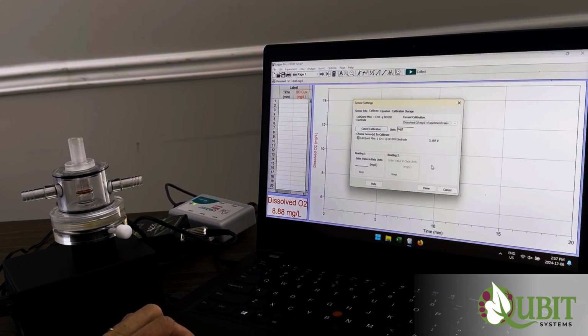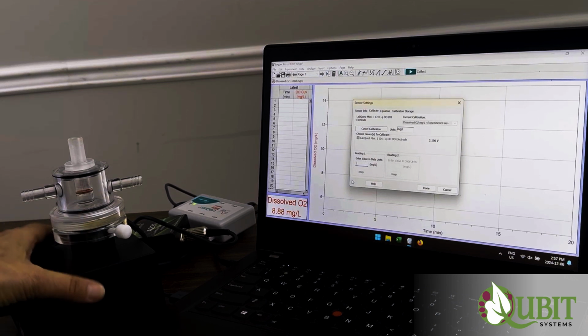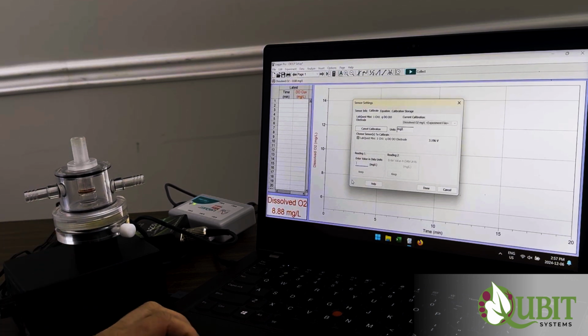It's a 2-point calibration, it's a linear calibration, and you will see reading 1 and reading 2. Reading 1 will be the first reading that we obtain, which is air saturated water, which is what's in the electrode right now. You'll see the voltage associated with that reading here, and you have to enter the value in milligrams per liter, which is the unit that we are using in this file, for the level of oxygen in air saturated water at the current temperature, which in this case is 21 degrees, and current atmospheric pressure.